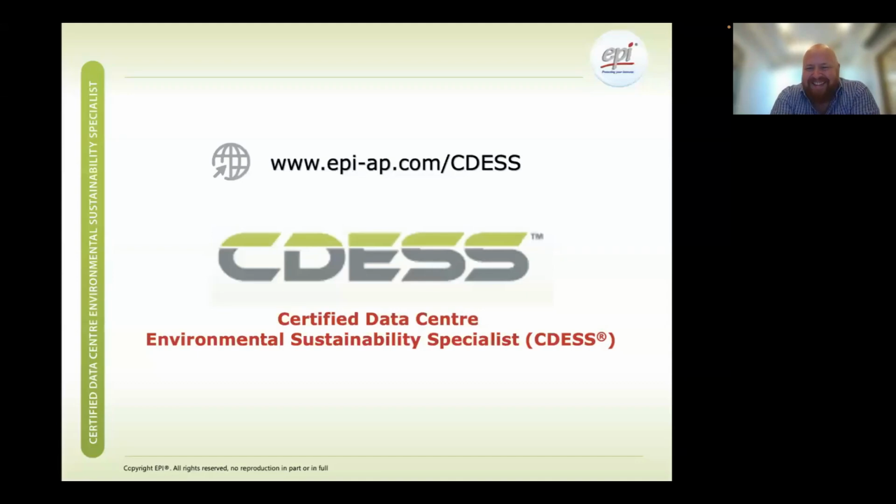Of course, we will also go into greenwashing, as they call it, boosting the environmental performance of a data center. We already mentioned the renewable energy certificates, which are under a lot of discussion, but also people measuring the PUE of a data center during the winter time and saying this is our average PUE, when it is actually the PUE on a very cold day, just to attract customers for a commercial data center.